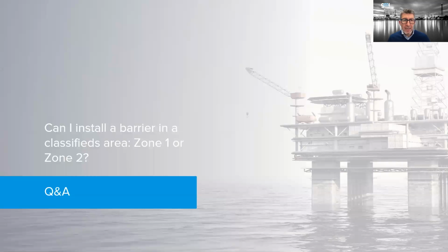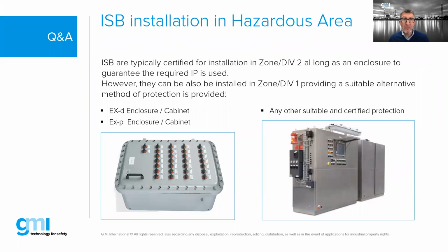Coming back to another question which we answered live a little bit earlier: can I install a barrier in a classified area, zone 1 or zone 2? Well, not the same question we got earlier, but in a way, yes, you can, using the proper enclosure. Many barriers, for example the GMI range of products, are dual marked from an Ex perspective. They're marked as an associated apparatus providing protection downstream, but they're also marked for where they can be located. GMI's product is certified Ex ec, or the old protection concept Ex nA, which is non-arcing. So the barriers themselves are suitable to be mounted in a zone 2 environment.